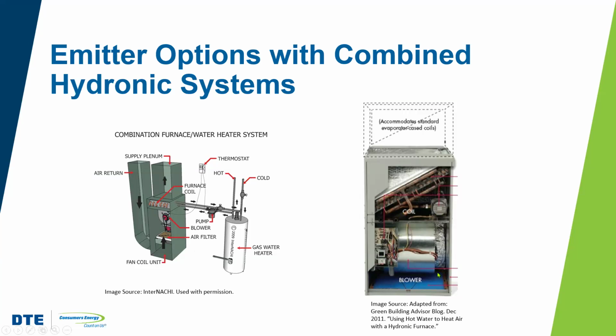You've got your two compartments, but instead of having a heat exchanger, where you're burning natural gas to generate heat, here you have a hot water coil, right? So you're taking hot water and you're sending that over there. You're blowing the air over that hot water. So it's very similar to a forced air furnace system, and it is a forced air system. It's just not using a furnace, right?